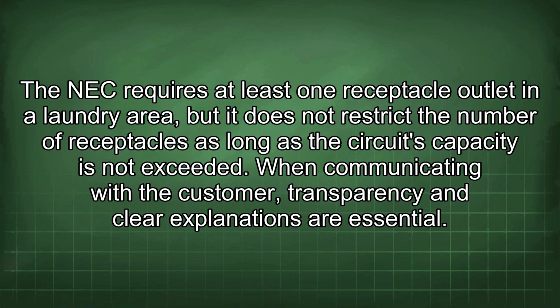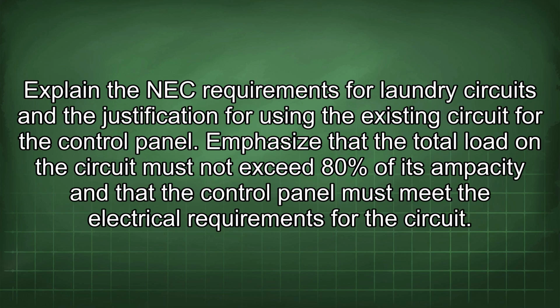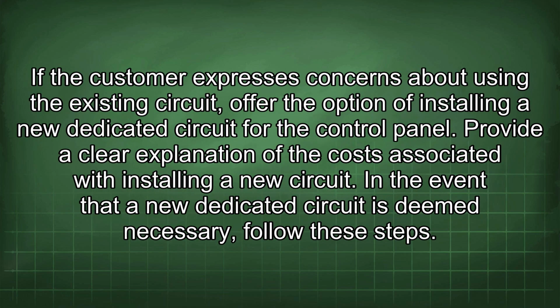When communicating with the customer, transparency and clear explanations are essential. Explain the NEC requirements for laundry circuits and the justification for using the existing circuit for the control panel. Emphasize that the total load in the circuit must not exceed 80% of its ampacity and that the control panel must meet the electrical requirements for the circuit. If the customer expresses concerns about using the existing circuit, offer the option of installing a new dedicated circuit for the control panel. Provide a clear explanation of the costs associated with installing a new circuit.